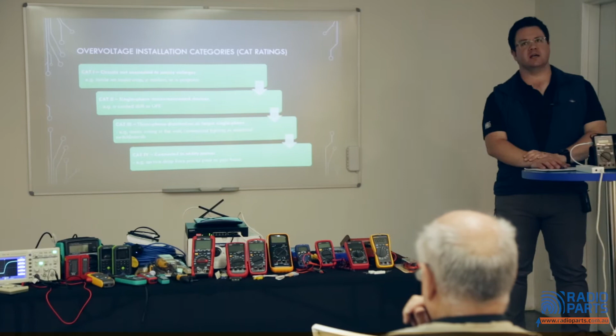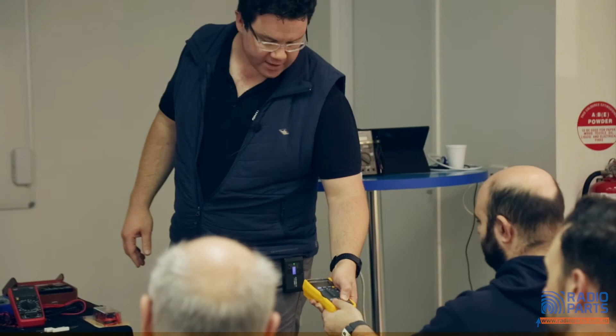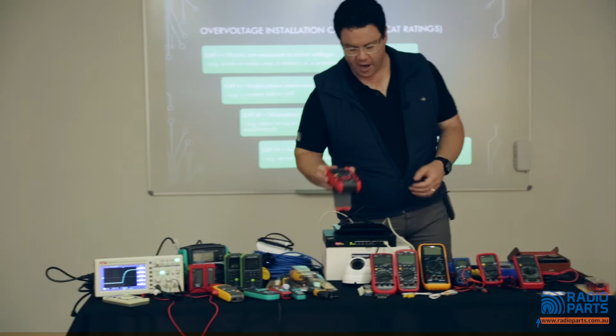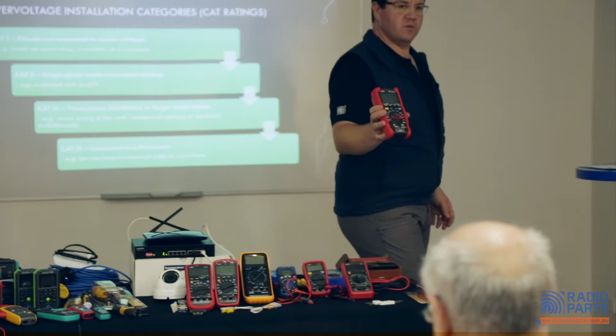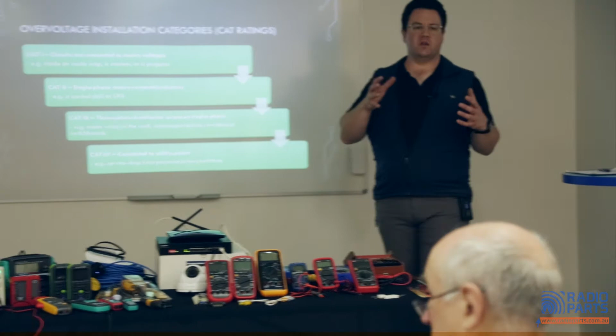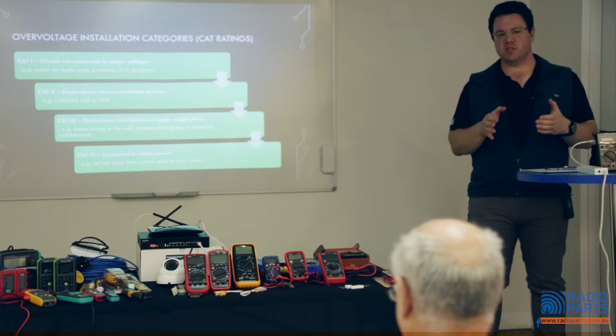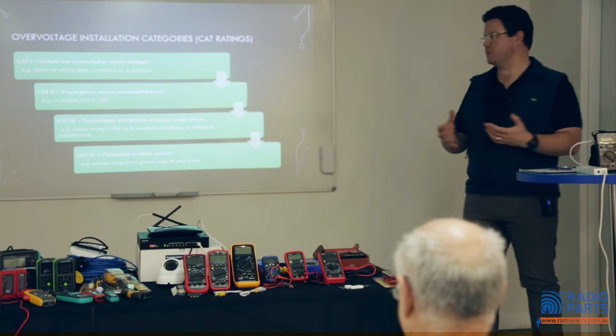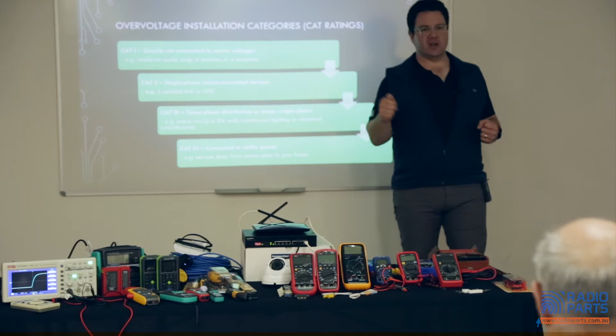CAT ratings. CAT ratings are less about the voltage that's on a component. If you have a look at, say, this will do—this meter has got CAT ratings on the bottom of it, and you can see there what they are. All of the meters up here have got different CAT ratings on them. Some have got different CAT ratings depending on which actual outlet or which testing you're actually putting them through. Now, a CAT rating is about where you are doing your testing in relation to the mains voltage from the outside world. I'll make it simpler, but essentially it comes down to the capability you have of having something go wrong in terms of a voltage spike. So it's less about what you're measuring and more about how isolated you are from something that's really going to hurt you and really going to try and take you out.